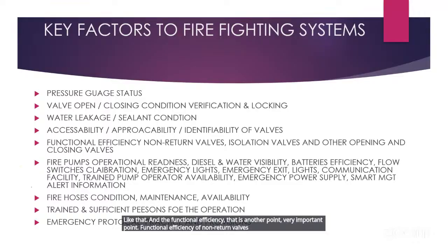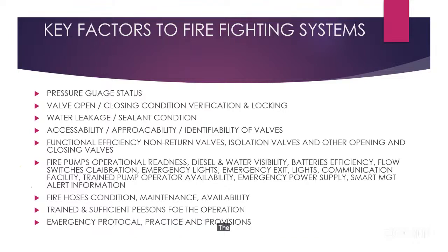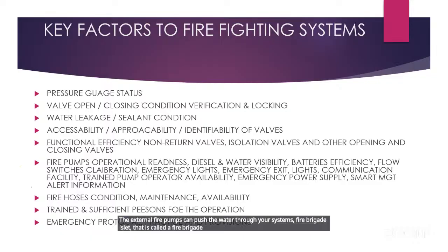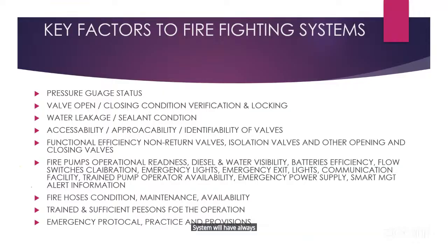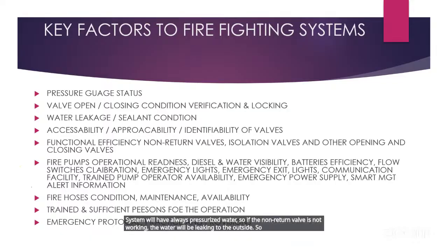External fire pumps can come and push water through your systems. That is called a fire brigade inlet. The system is connected to the fire brigade inlet, and the system will always have pressurized water. So if the non-return valve is not working, the water will leak to the outside. So the non-return valve must be tested.